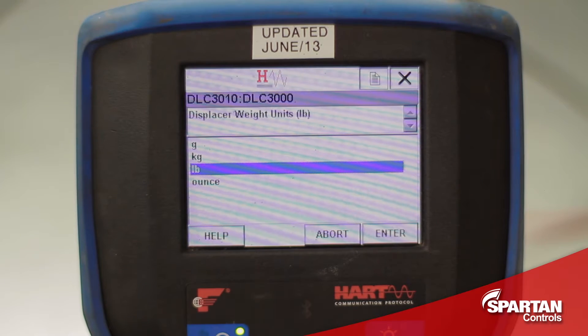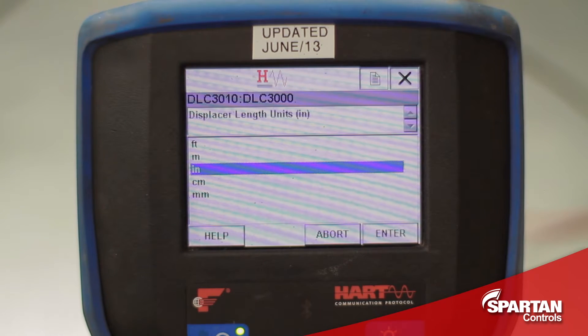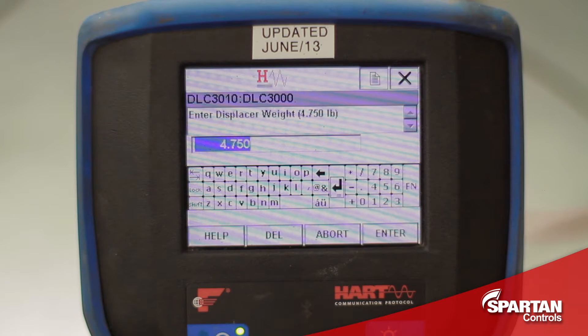I will choose displacer weight in pounds, displacer volume in cubic inches, and displacer length in inches because these are all the units that are given on the nameplate. A standard displacer weight for a Fisher displacer is 4.75 pounds as stated on the nameplate, but it is always a good idea to measure the displacer if you can.